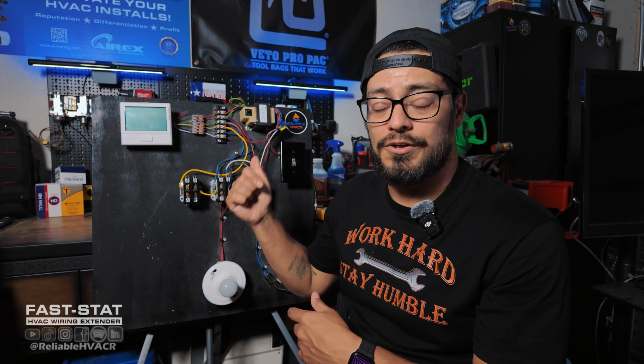You've got a short to ground, which either popped your fuse or your transformer, or you're going to have a broken wire. In that instance, everything else is working, but you're not getting cooling or heating, or you're not getting that 24 volts for that thermostat. So you're going to need to go through, and basically what I do first is make sure that we're calling.